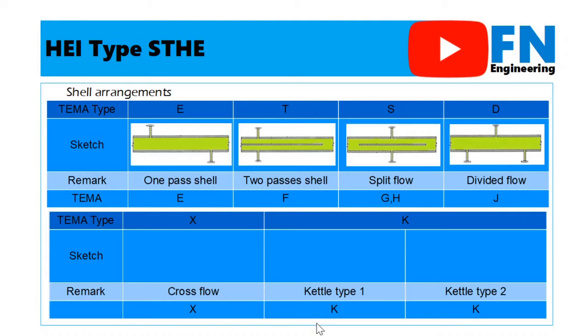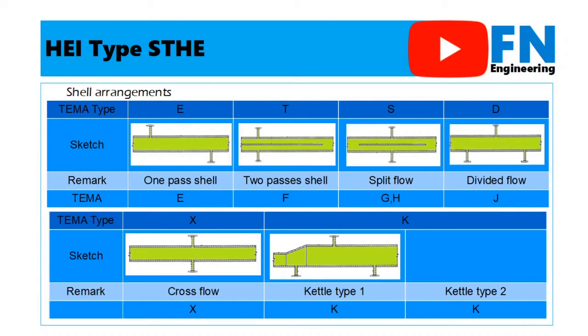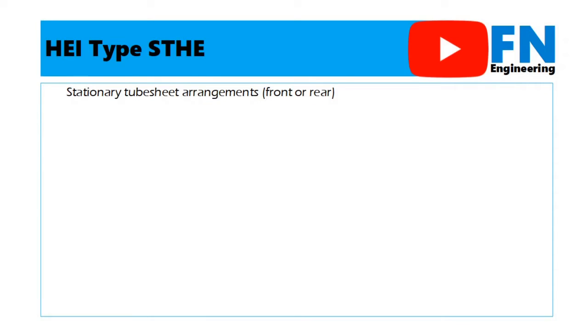The next type is type X for cross flow shell. It is the same type if we see the TEMA standard. And the last type is type K for kettle heat exchanger. There are 2 configurations for type K. It is with 1 reducer and 2 reducers. The next slide is identification for tube sheet.